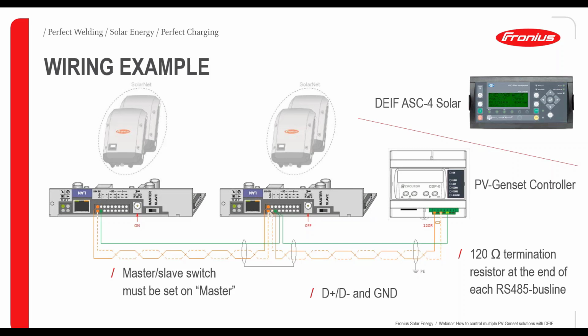When looking at the cabling down below, we can see a twisted cable pair. That is the first thing I want to recommend you. Please use a twisted cable pair for the Modbus communication. Between data plus and data minus, these should be a twisted pair. Also, we can see a grounding that is done. In this area underneath the controller, we can see that the shield of the cable is grounded on one side, which is again a way to ensure the perfect data communication. Then another part is what is written down left. Switch every data manager to master. That's essential to switch them to master, because only then the data will be sent to the controller.